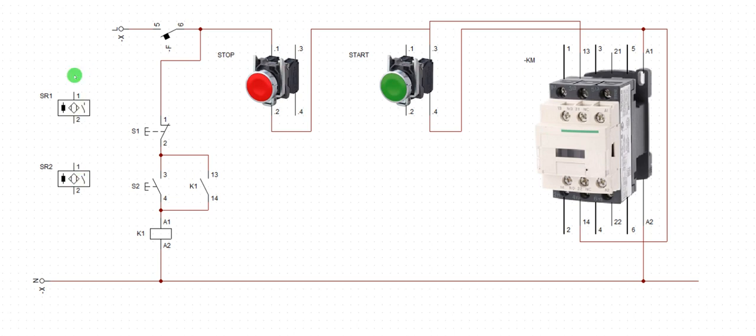So what we are going to do now is to incorporate our sensor. Now, in some systems, you will have this setup already, enclosed in a control system. You have a panel, and you incorporate this into the panel. The essence is this: if this one fails, you can manually operate that same system. And there's always a stipulated law that every automated system must have a manual override system. For instance, you have an ATS, automatic transfer switch, that starts your diesel generator when the utility supply is inactive. If you have such a function, you should also create an override on that same ATS, so that when the contactor fails to close, you have a means of sending power to the output side of the load.